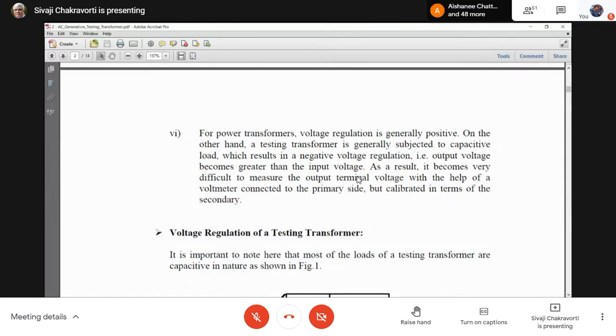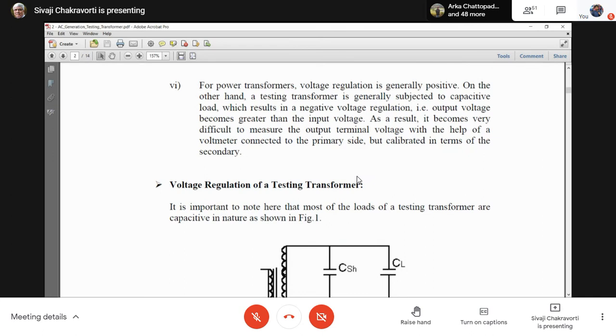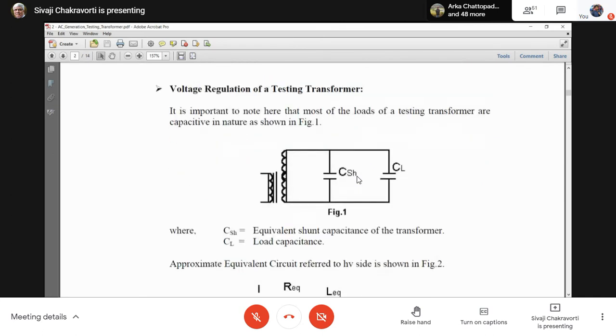They also know that. But that's where their knowledge stops, and that's where the engineer's knowledge should come. Why do I stop at 26 kV? I, being the testing engineer, know why it has to be stopped at 26 kV. That makes me the one in charge of the testing. Otherwise, I remain only a technical staff, I don't become a testing engineer. That is another aspect I always try to highlight, that there is a big difference between the technical staff and the engineer.